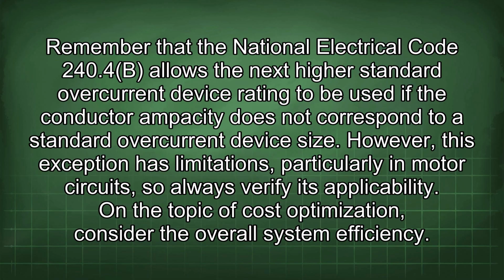Remember that the National Electrical Code 240.4(B) allows the next higher standard overcurrent device rating to be used if the conductor ampacity does not correspond to a standard overcurrent device size. However, this exception has limitations, particularly in motor circuits, so always verify its applicability.